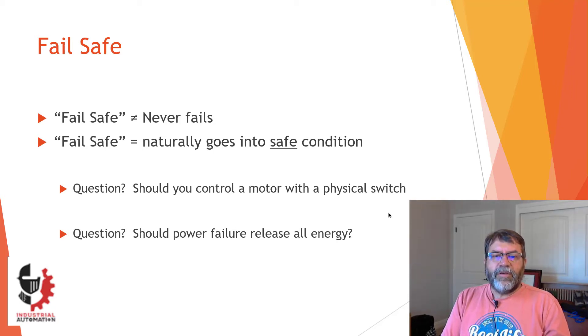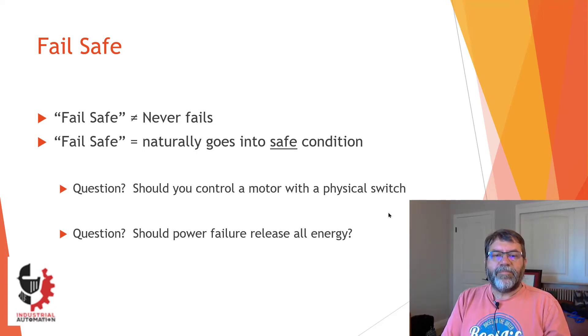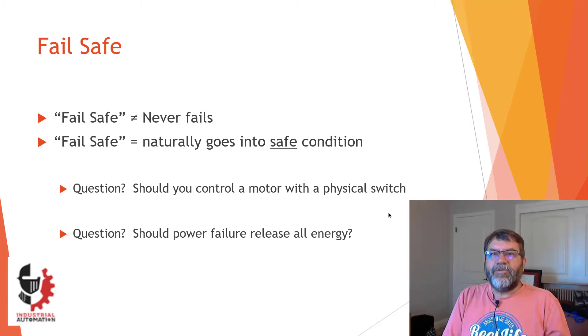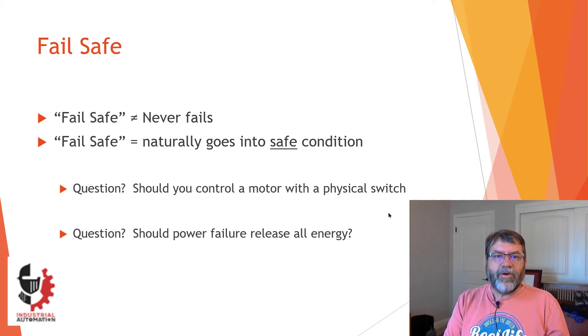But maybe a sump pump — something that pumps out water from a crawl space — you want that to be able to come on automatically. So it depends on what you're controlling. Another question you have to ask yourself is: if you have a power failure or you hit your e-stop, should that automatically release all the power in the system? If you have a pressurized tank, should you release the pressure or just close the valves and lock the tank down? There's no one-size-fits-all answer — you have to consider your application and think about what should happen on a failure.